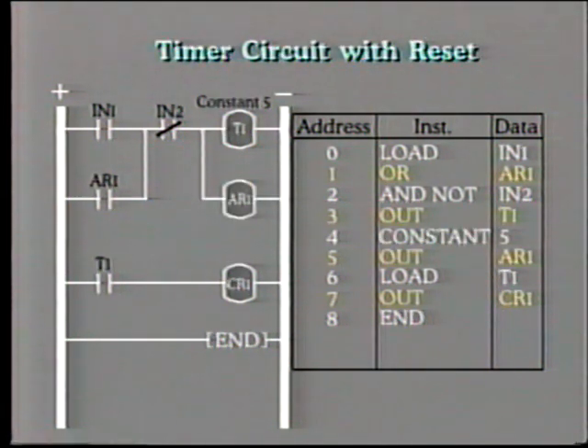This example shows the inclusion of a timer. When the push-button contact IN1 is closed momentarily, it is sealed in by the auxiliary relay. The timer is started, and after 5 seconds, the timing relay contacts close, energizing the control relay output. However, if the IN2 relay becomes energized during the delay period, its contacts will open. This breaks the seal-in circuit and de-energizes the timer, thus resetting it to 0. The IN2 contact is probably a permissive for the particular control device. In effect, during startup, this circuit is allowing the permissive 5 seconds to check conditions before allowing the start to proceed.